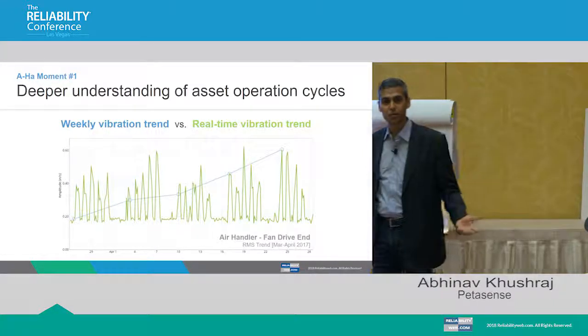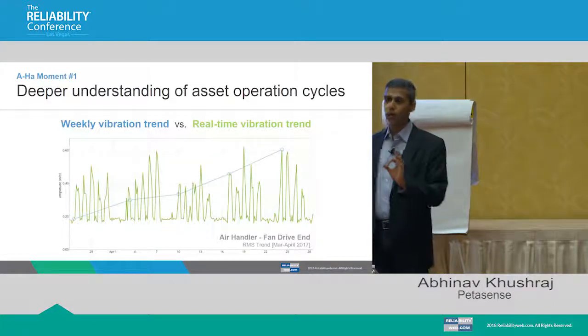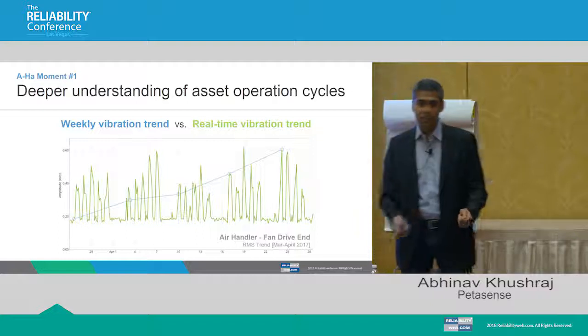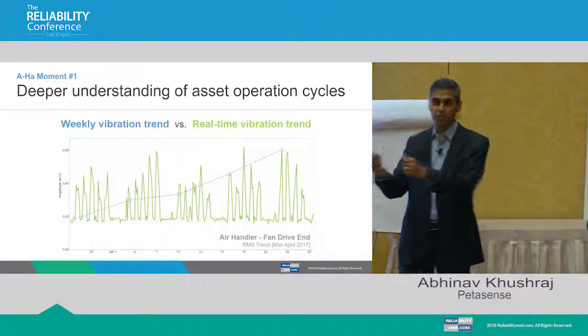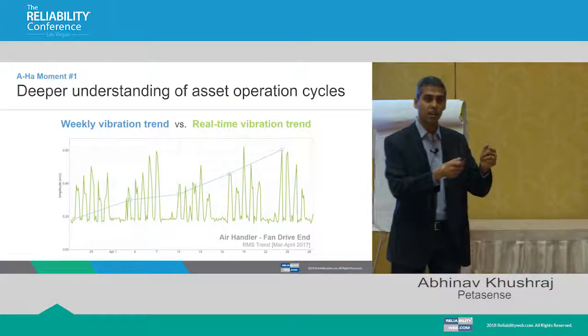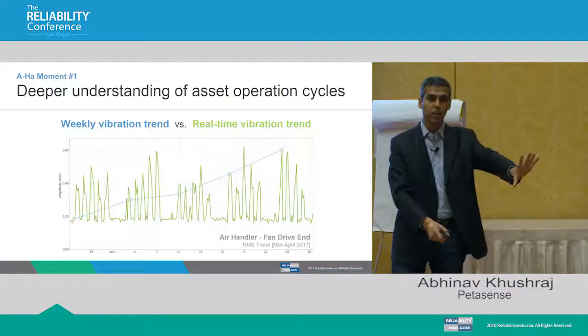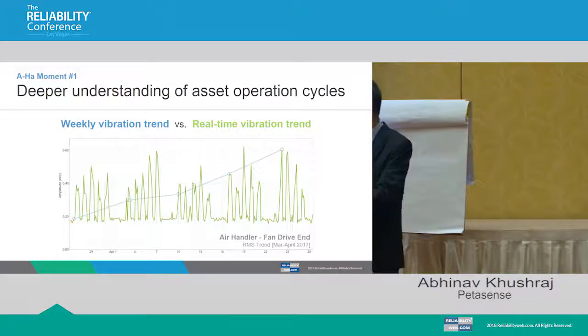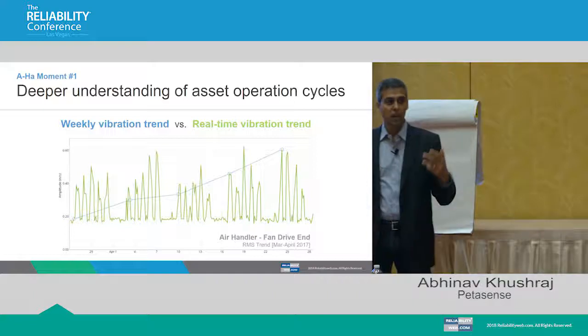So what's happened in this case is operations data is now readily available to you on a predictive maintenance system. And why is that valuable? Because 101 of vibration science: you can take vibration readings, but if you take it in situation 1, the load is very different from situation 2, as was the case in the blue line. You will have the wrong results.